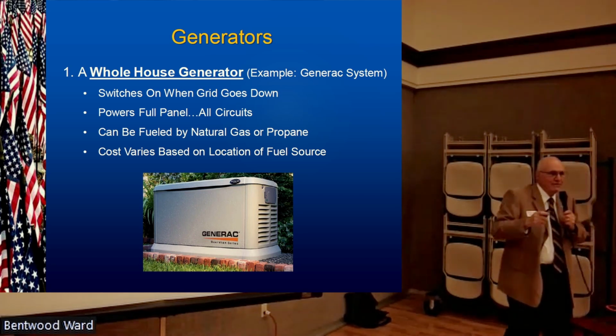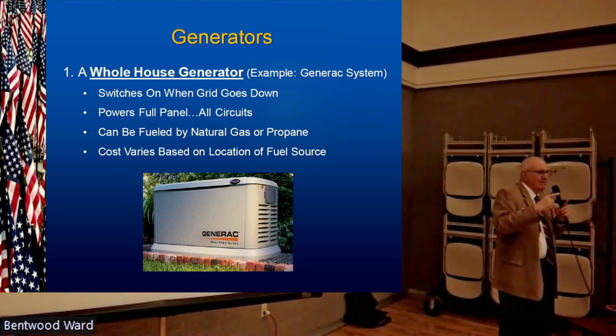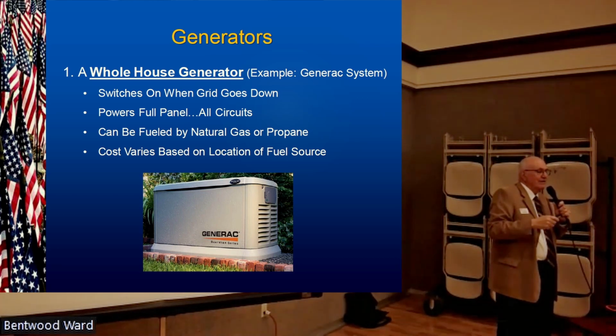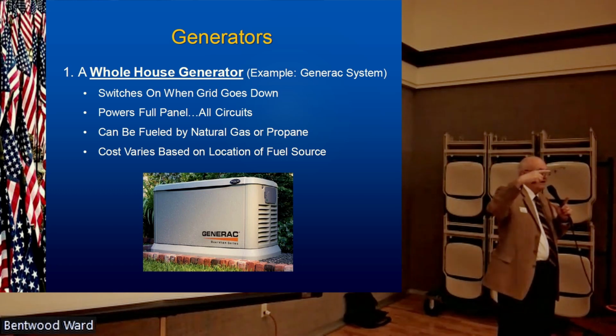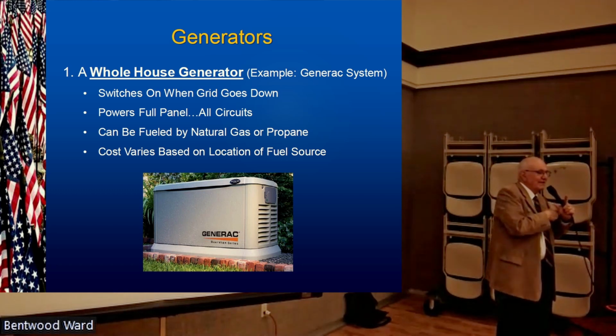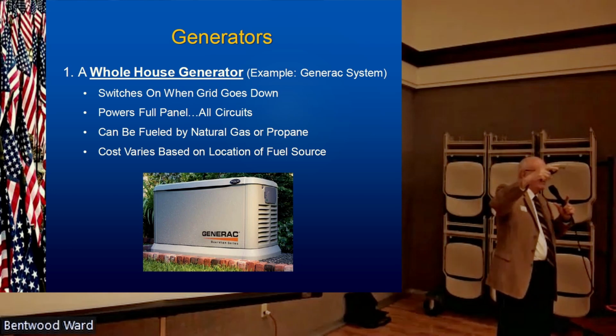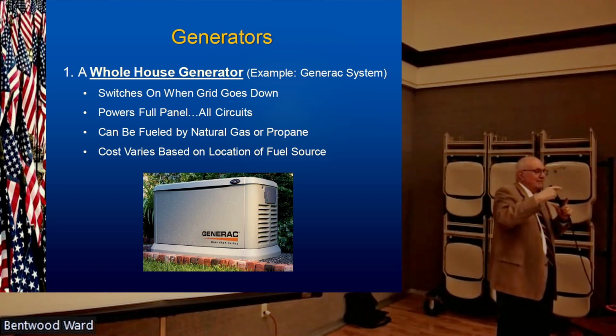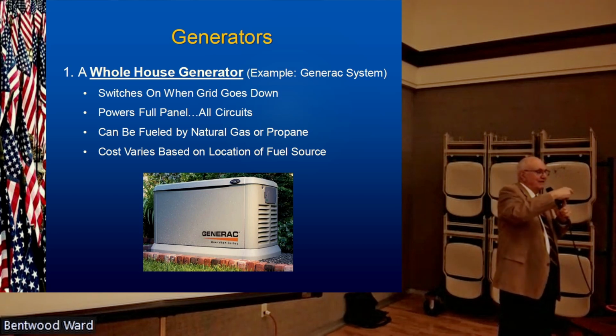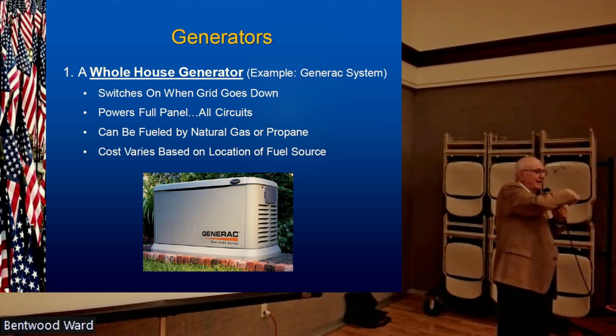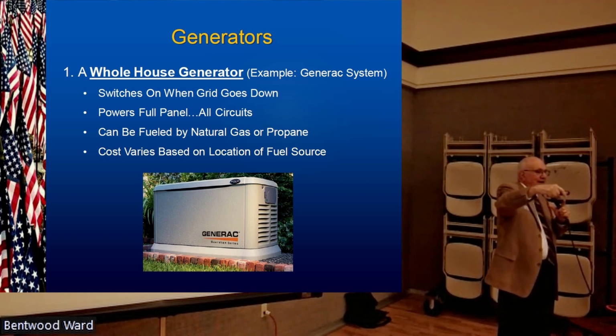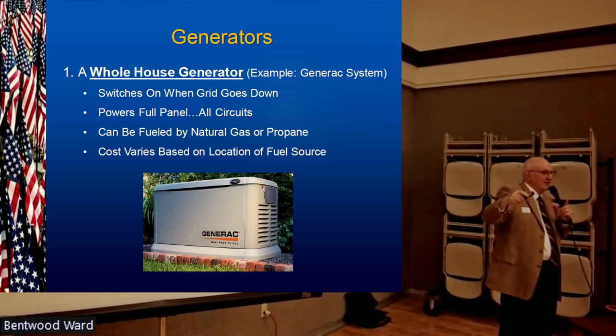If you're thinking about one of these, and you've got a square house, look for where your electrical panel is on the outside of the house, then look for where your natural gas comes into the house. 80% of the time it's on the cat-corner side of the house. So if you want to fuel a generator with gas, you've got to run a new gas line, get a new higher capacity meter from the power company, and run the line all the way around the house to get to where the Generac is.